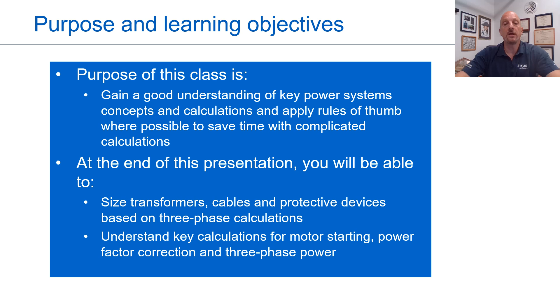This is on basically rules of thumb and calculations that you'd like to know for doing consulting work in the power systems field. So we're going to talk about transformer calculations, fault current calculations, and so forth. The purpose and learning of this session is really to gain a good understanding of the key power system concepts and calculations that apply, and basically around rules of thumb. So if you're thinking about the person sitting next to you that's been in their job for a long time, we want you to understand how do they come up with these calculations. At the end of this presentation, you'll be able to size transformers, cables, and protective devices based on the three-phase calculations. And also to be able to understand the calculations for motor starting, power factor correction, and three-phase power.